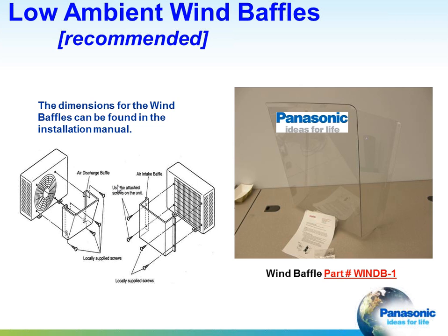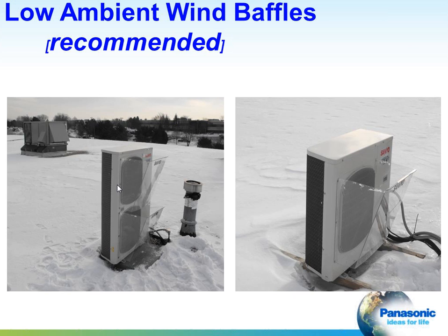So whenever you install these units, low ambient wind baffles are highly recommended. Save yourself a trip going back, put it on when you install the system. And here's the other reason that you want to put these on: it helps avoid snow buildup against the unit.